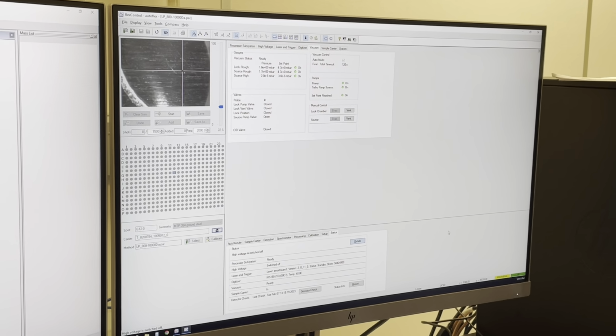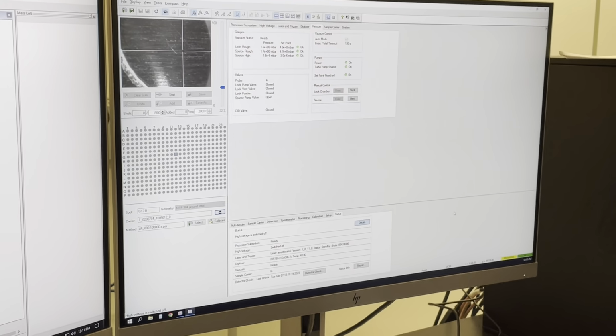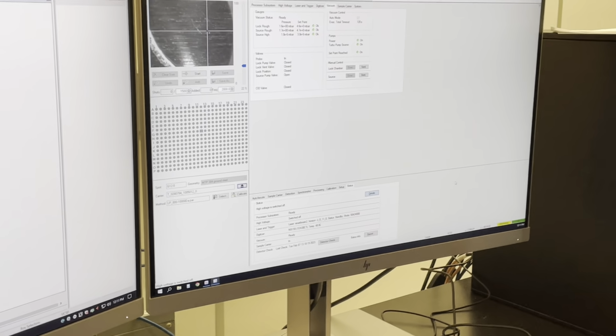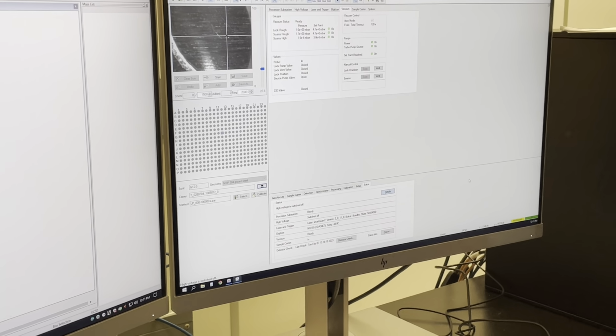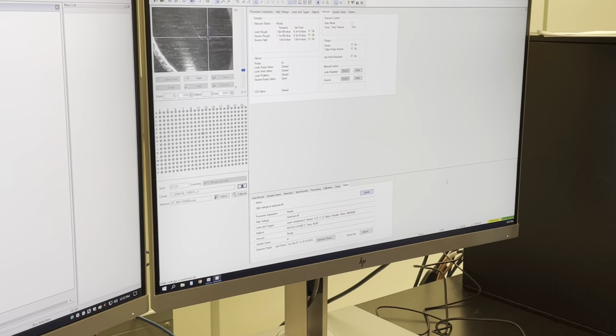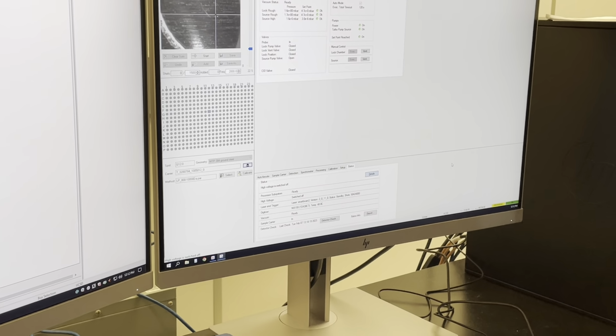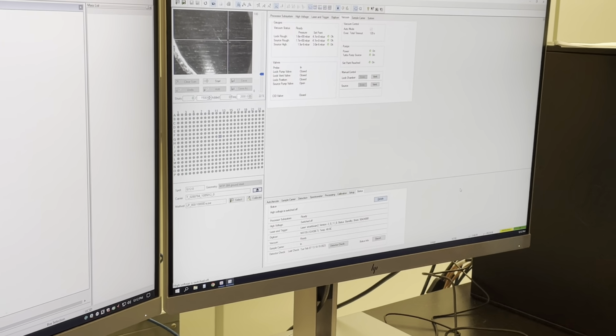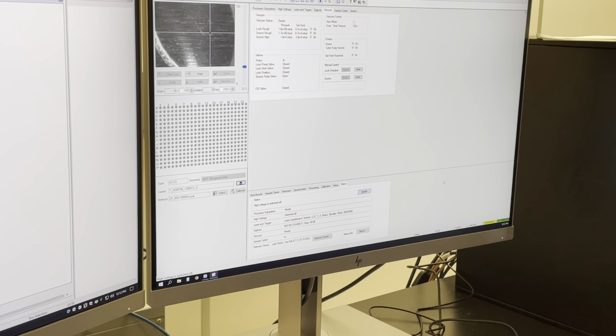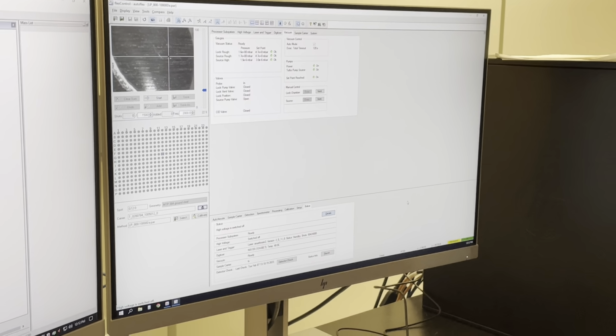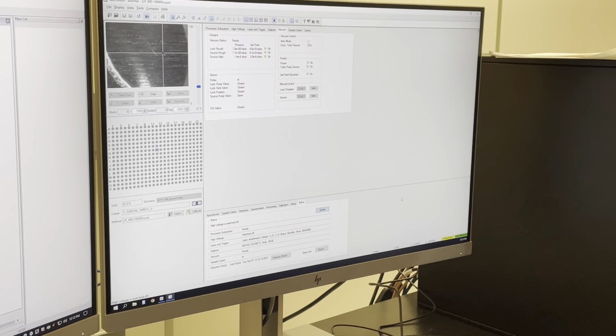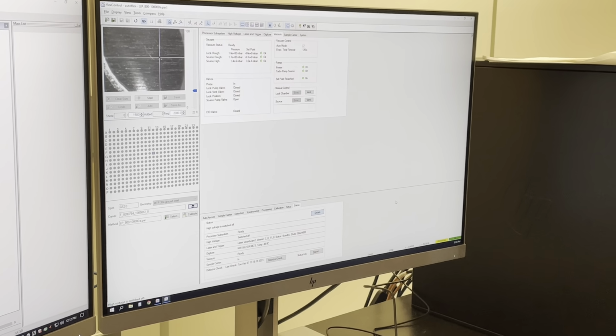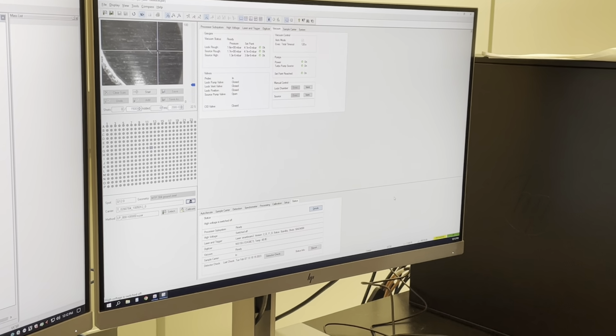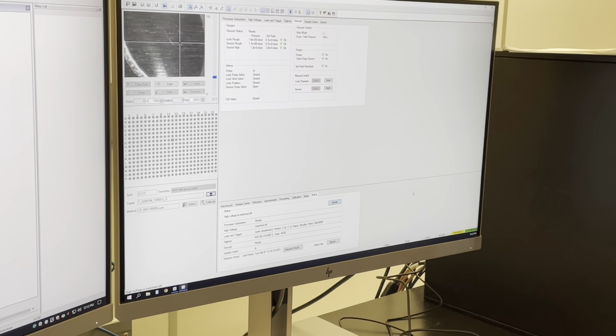The reason to have a good vacuum inside the source is that for MALDI-TOF, they use a high voltage, 20,000 volts, and the vacuum needs to be good, otherwise it may cause arcing, and that's going to damage the electronics. And right now we don't have a service contract. Everything needs to count on our users to take good care of the instrument. Otherwise, if something happens to the machine, we have to pay the repair cost, and it's very expensive.